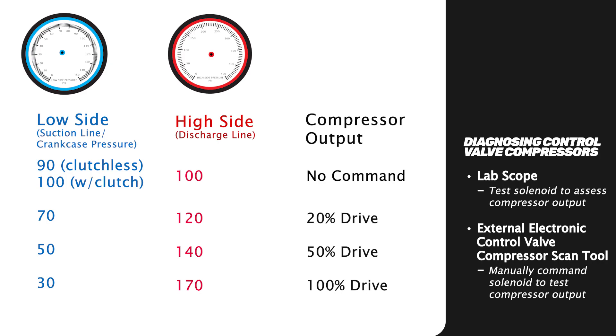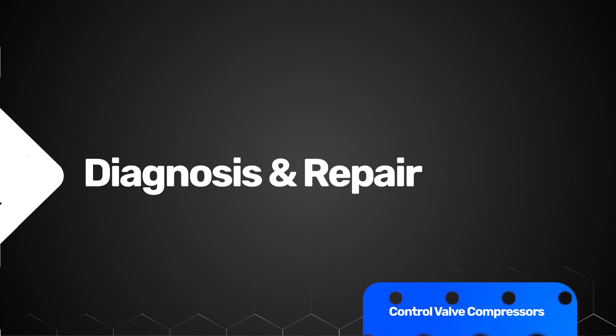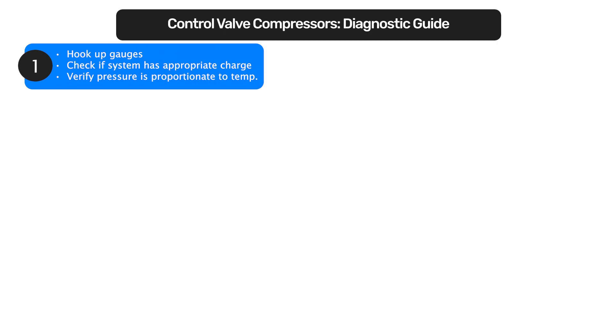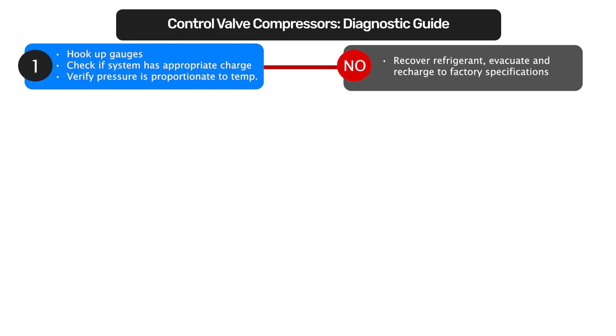The following guide lays out a step-by-step process to narrow down the source of failure. This is a general guide, not to be considered extensive. Always refer to the manufacturer's specifications for all components and equipment used. First, look at the gauges to verify charge and check if pressure is proportionate to temperature. If not, recover and recharge the system to factory specifications.